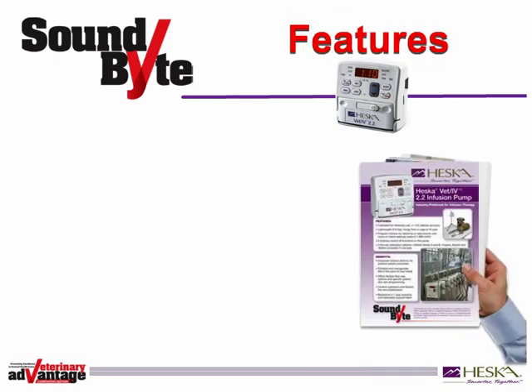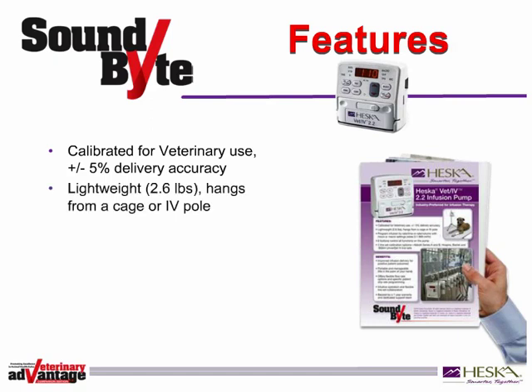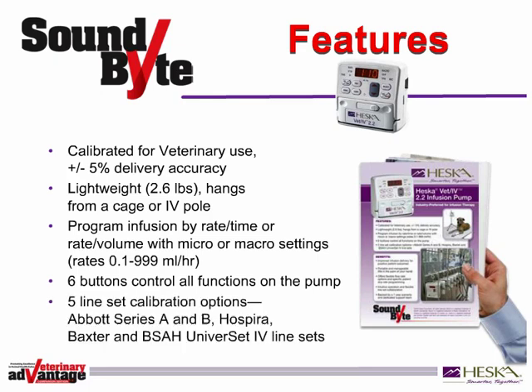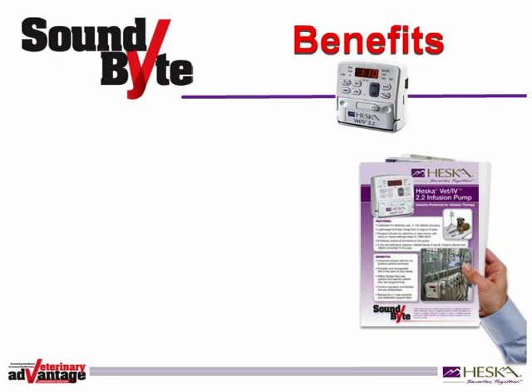Starting with features, you might say something like, 'The Heska Vet IV 2.2 pump is calibrated for veterinary use with a plus or minus 5% delivery accuracy. It's lightweight, just 2.6 pounds, and hangs from a cage or IV pole. Users can program the infusion by rate, time, or rate-volume with micro or macro settings. Six buttons control all functions on the pump.